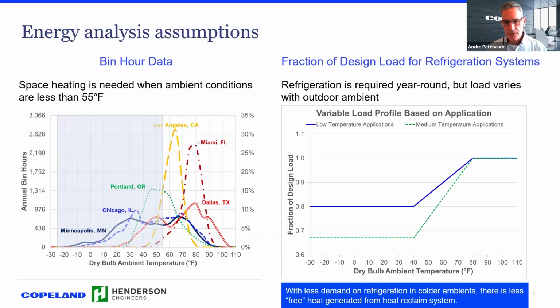So the reason we had to do that is because it's more real life, number one, and because we're using free heat, or condensing heat, in order to provide space heating, that amount of space heating starts going down. The availability of heat goes down, of course, as your load decreases in the winter. So we needed to factor that in. Next slide, please.